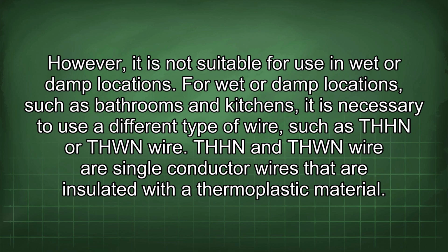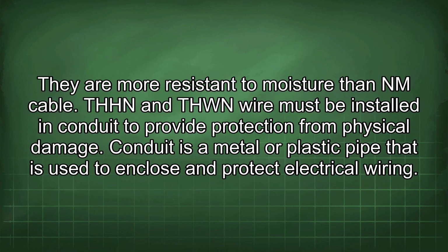For wet or damp locations, such as bathrooms and kitchens, it is necessary to use a different type of wire, such as THHN or THWN wire. THHN and THWN wire are single conductor wires that are insulated with a thermoplastic material. They are more resistant to moisture than NM cable. THHN and THWN wire must be installed in conduit to provide protection from physical damage. Conduit is a metal or plastic pipe that is used to enclose and protect electrical wiring.